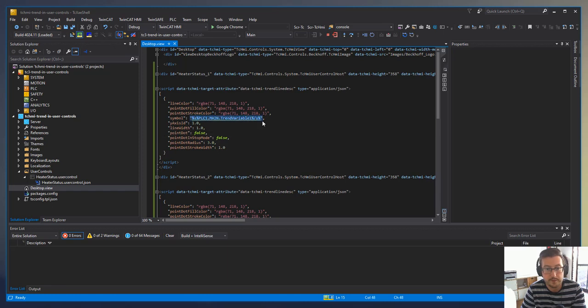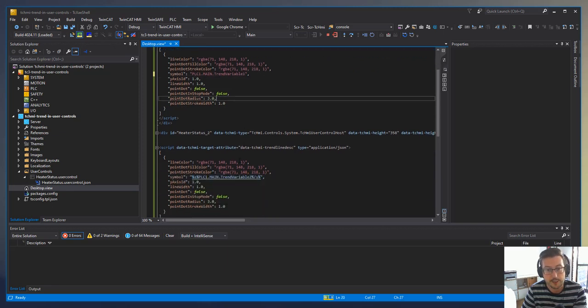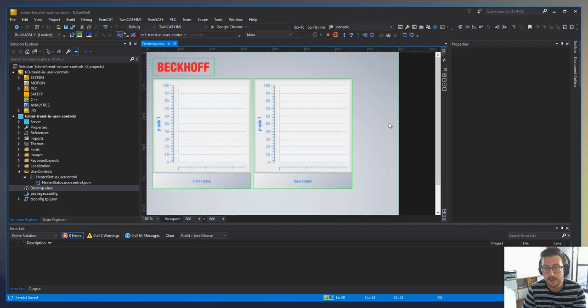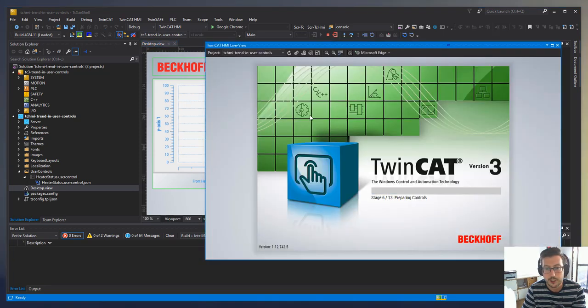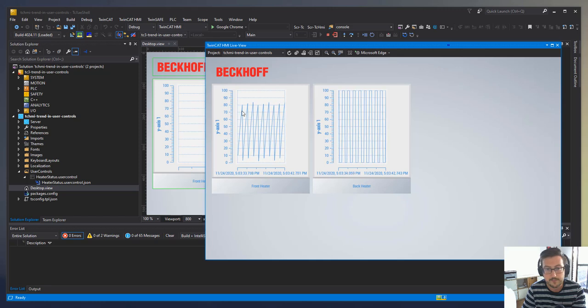And you can see here's the symbol we passed in, and it's been padded out to try to resolve the base value. So what we need to do is remove the percentage signs and just turn it straight back into its string, which is just going to say, no, this is the symbol I want you to historize. And I think most people would have got to this step on their own, and it's just this last step that causes an issue. We're going to swap back onto this main view here, and if we go onto live view, it should show that we've got working trends.